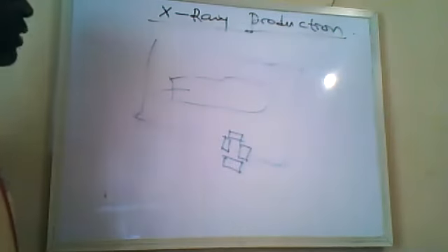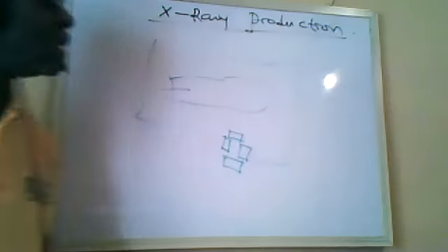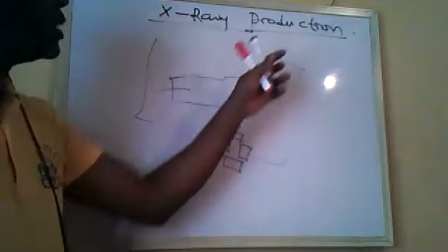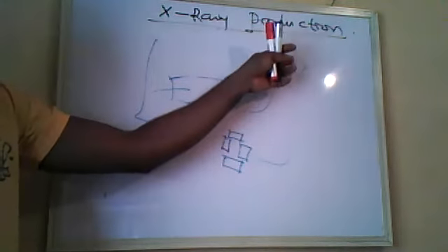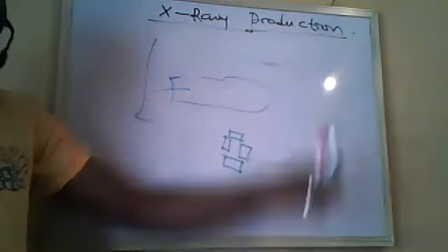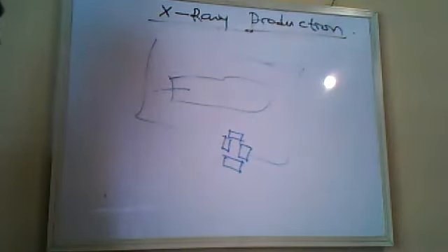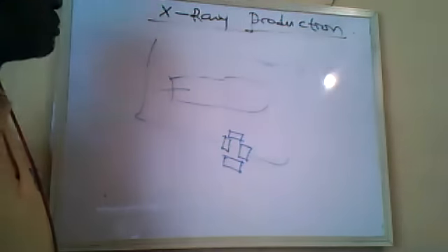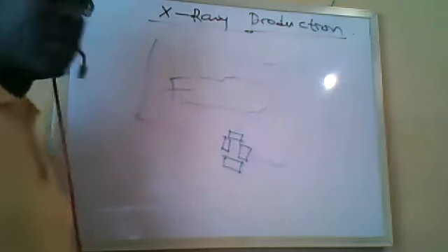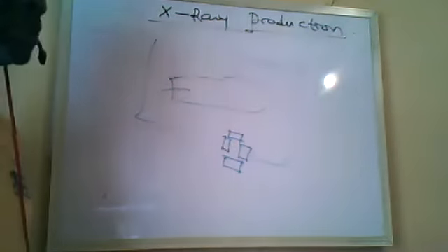So the next one is our X-ray field. And again, when it comes to this shielding, at times when we are doing our quality control or quality assessment, we need to calculate the leakage radiation from this tube. Because in as much as we have the lead shielding, at times the lead shielding might not be adequate, but I wonder why. That shouldn't happen anyway.